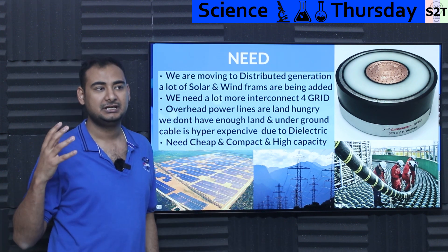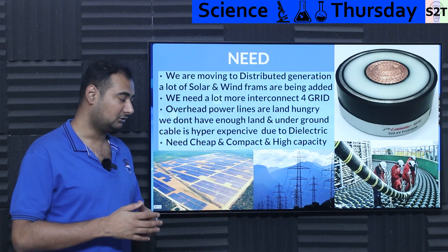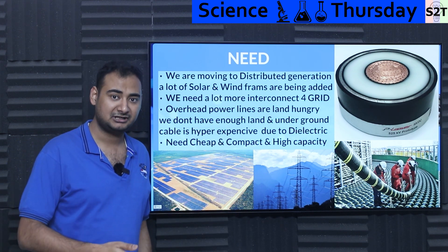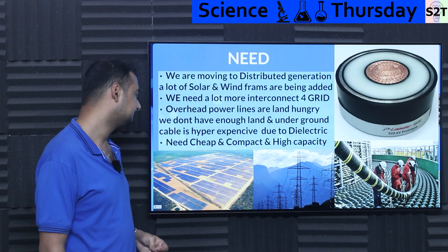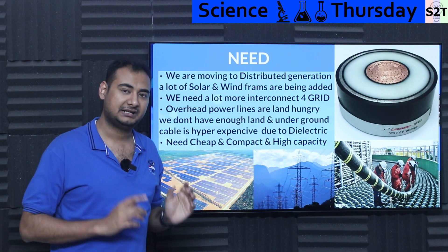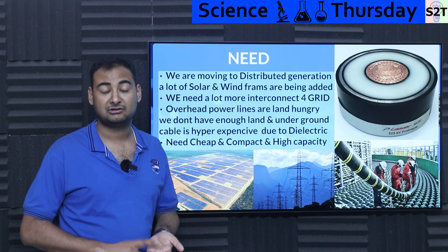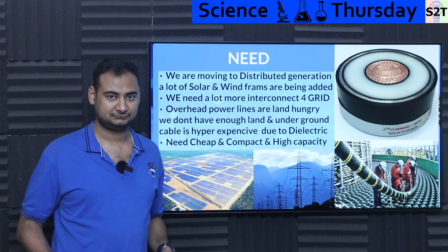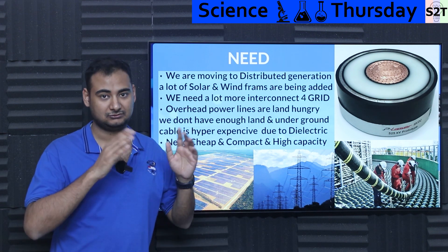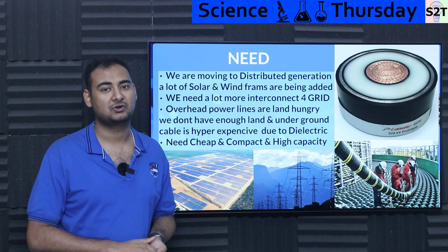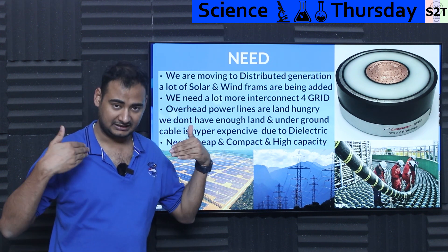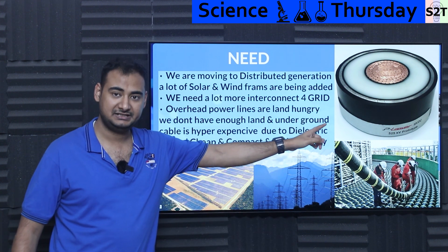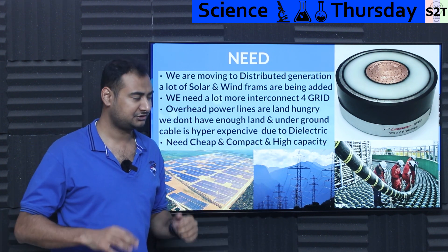If you have to carry 10 gigawatts of power to Delhi or Frankfurt, good luck — it's going to take an insanely large amount of land. You simply cannot have enough land area. You don't want to take away hundreds of hectares of farmable land for transmission lines. What about underground AC cable? You can bury it, but it's generally not recommended because underground AC cable has much worse capacitance properties and loses a lot of power — it costs exponentially more per kilometer compared to overhead lines.